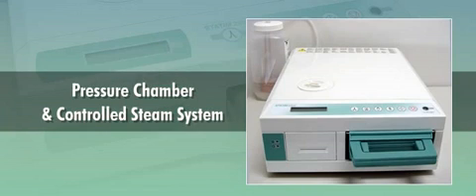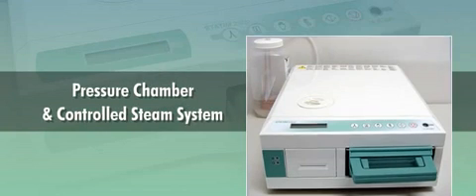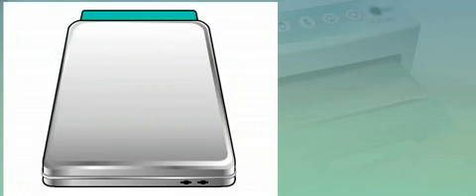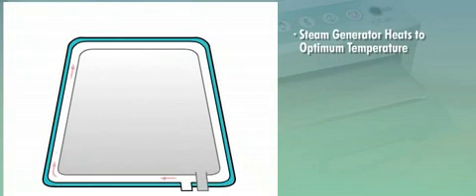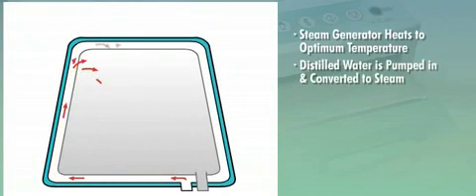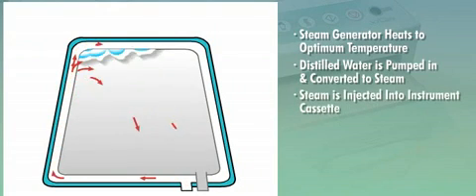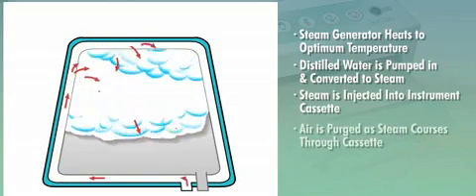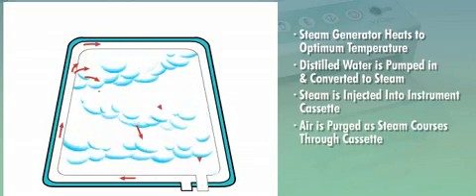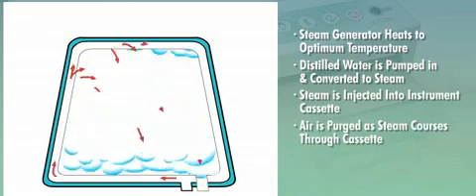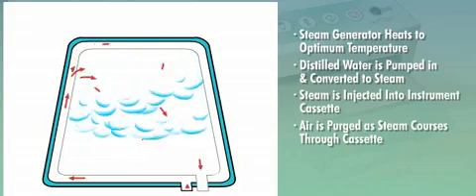The key to the STATIM's fast sterilization is in the unique design of the pressure chamber and controlled steam system. No water chamber needs to be heated, saving valuable time. When start is pressed, the steam generator heats to the optimum temperature and distilled water is pumped in and converted to steam. A wall of steam is then injected into the instrument cassette. Air is purged safely as the steam courses through the cassette and is expelled into a condenser bottle.